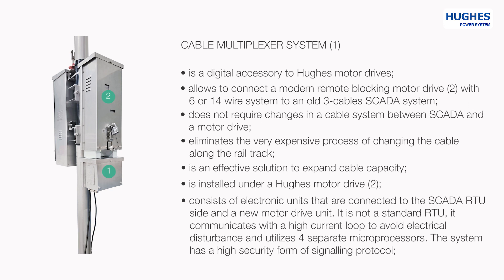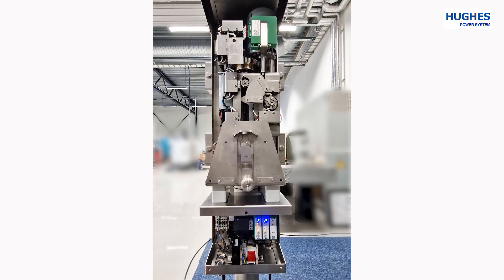The Cable Multiplexer System is installed under a Hughes motor drive. It consists of electronic units connected to the SCADA RTU side and a new motor drive unit. It is not a standard RTU — it communicates with a high current loop to avoid electrical disturbance and utilizes four separate microprocessors. The system has a high security form of signaling protocol.